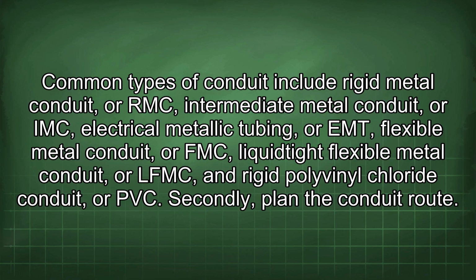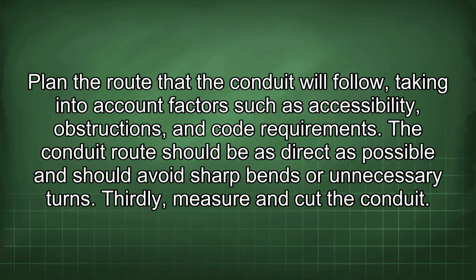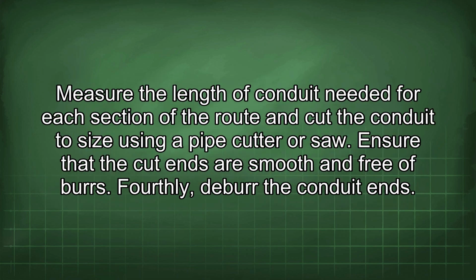Secondly, plan the conduit route. Plan the route that the conduit will follow, taking into account factors such as accessibility, obstructions, and code requirements. The conduit route should be as direct as possible and should avoid sharp bends or unnecessary turns. Thirdly, measure and cut the conduit. Measure the length of conduit needed for each section of the route and cut the conduit to size using a pipe cutter or saw. Ensure that the cut ends are smooth and free of burrs.